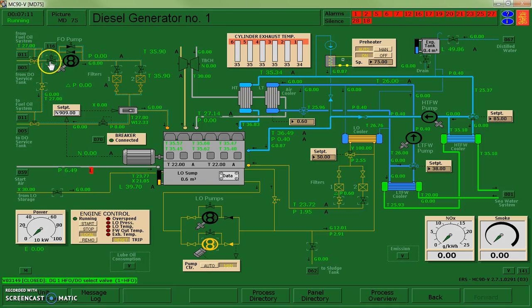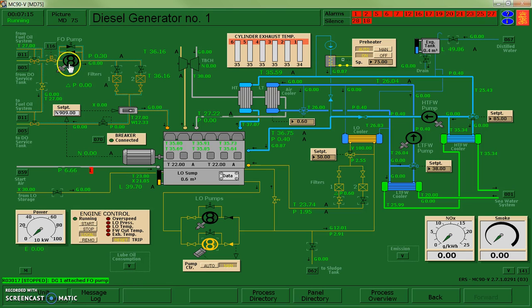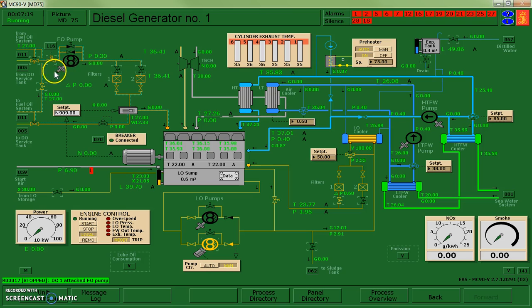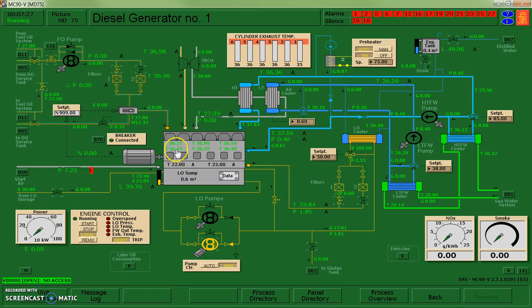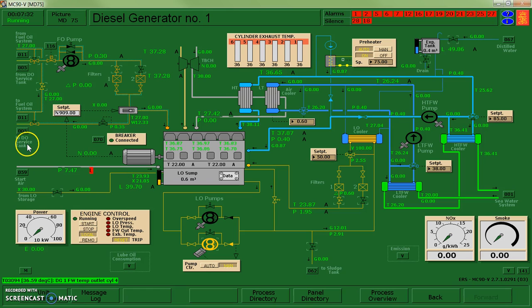So if I keep following through, sometimes I need to adjust this valve position. Right now it's in line. I've got another shutoff valve. Pump is going to be activated automatically by the rotation of the engine. So I don't need to turn that guy on. And I've got a filter to pass through. And that will give me access to the engine or recirculating back to the diesel oil fuel service tank.